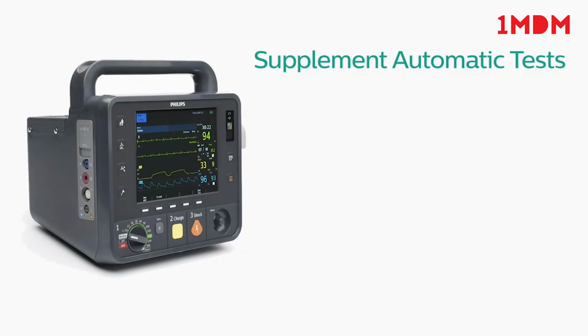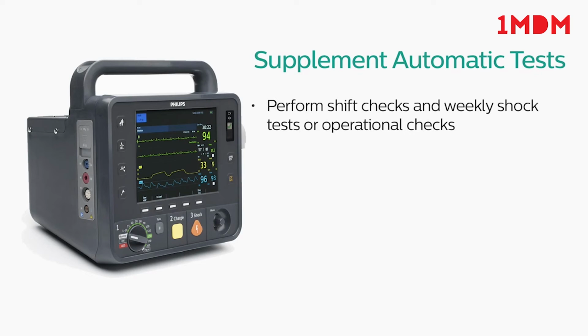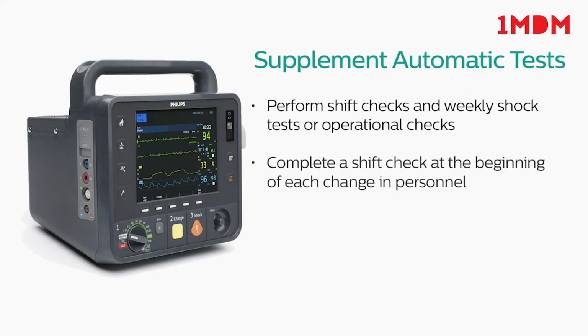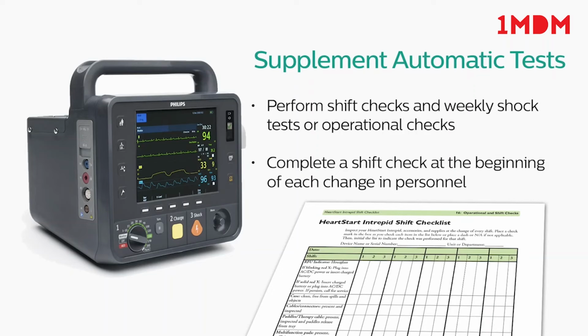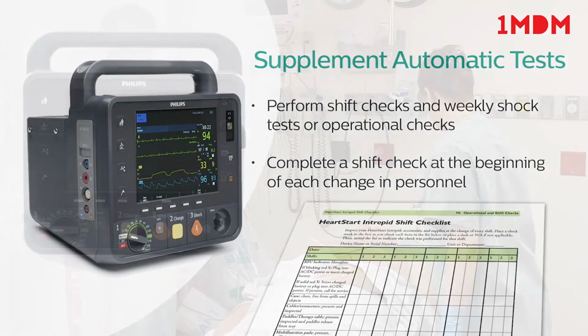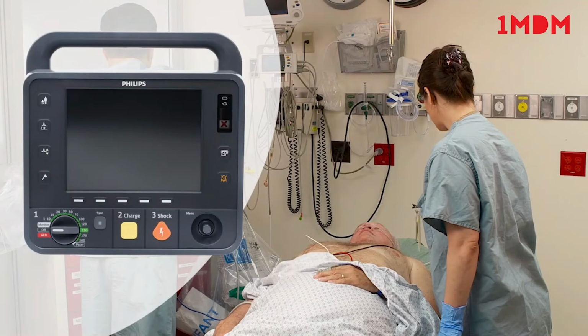To supplement the automatic tests, you should perform shift checks and weekly shock tests or operational checks on the device. Philips recommends completing a shift check at the beginning of each change in personnel to help ensure that defibrillators are ready when needed. Philips provides a checklist to complete a shift check on the HeartStart Intrepid, including the ready-for-use indicator and related accessories and supplies. You must make sure the HeartStart Intrepid is not connected to a patient when performing an operational check.